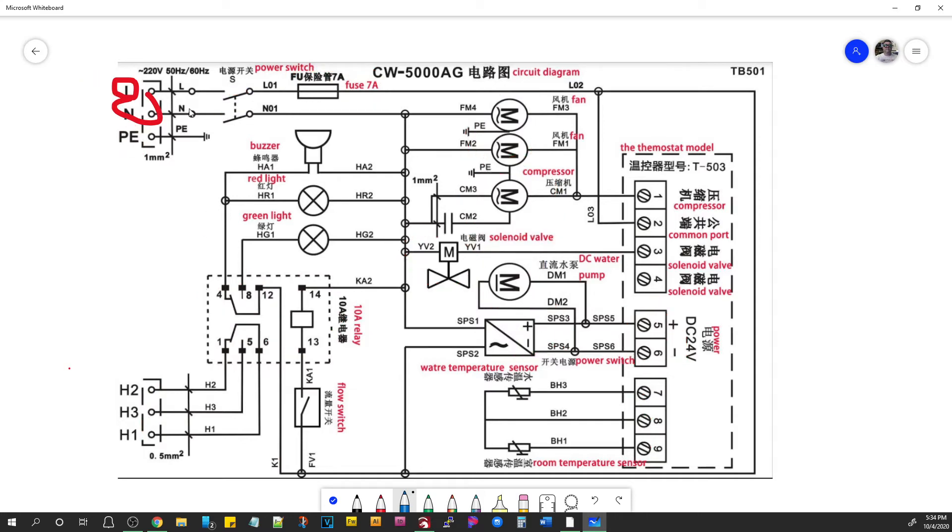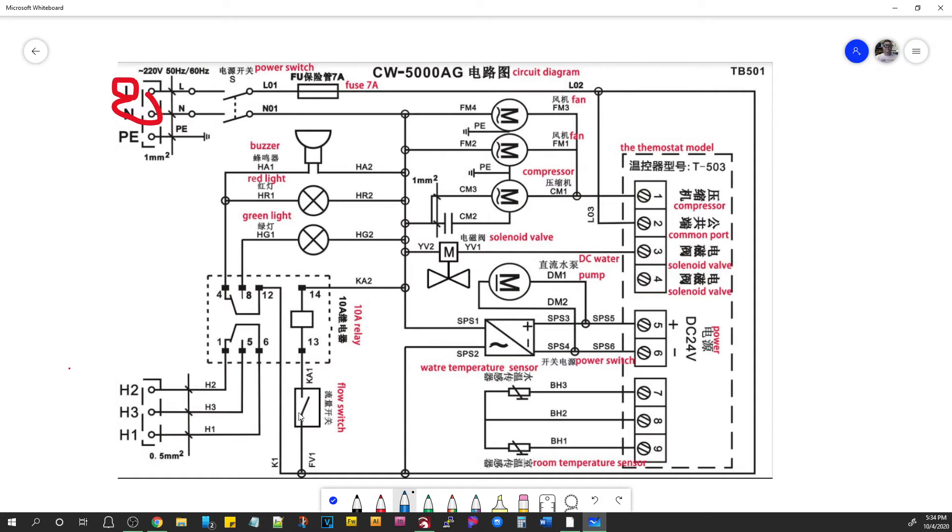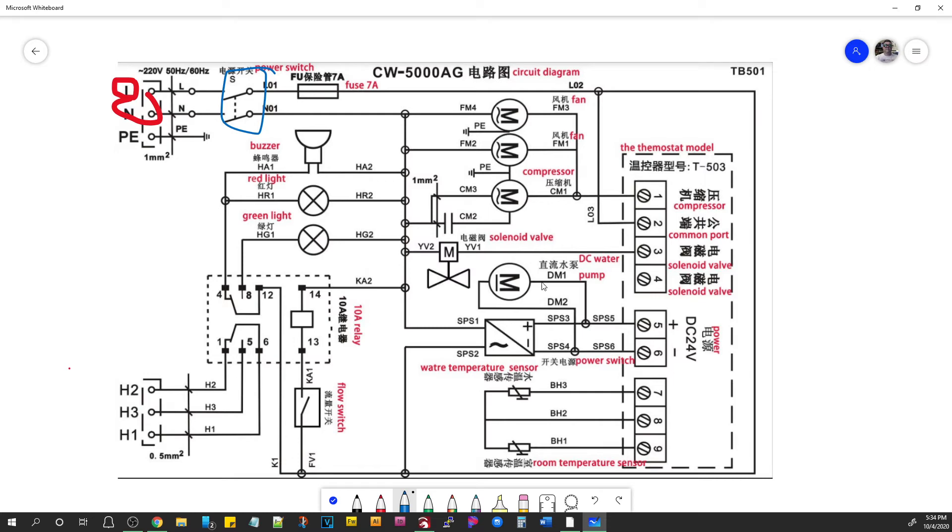So it comes in here. You turn the switch on. It energizes everything. Now, when you first turn it on, you get a buzzer and a red light. And the reason is this diagram is drawn as if it were in the off state. The switches are not engaged. There's no water flow because this circuit is not complete. And if you'll notice, these are normally closed positions. So that is red light and buzzer. When you energize the chiller, the water pump comes on immediately.